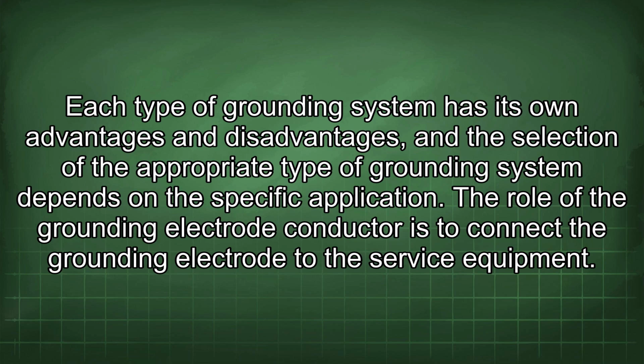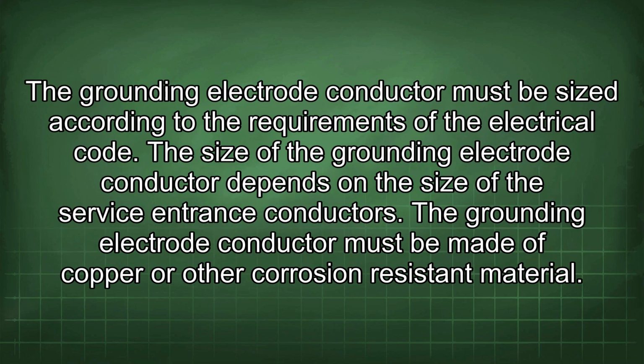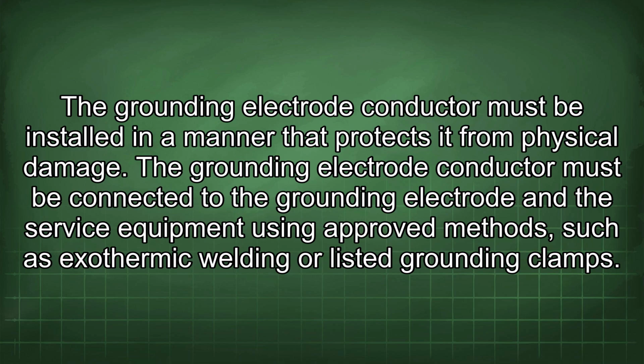The role of the grounding electrode conductor is to connect the grounding electrode to the service equipment. The grounding electrode conductor must be sized according to the requirements of the electrical code. The size of the grounding electrode conductor depends on the size of the service entrance conductors. The grounding electrode conductor must be made of copper or other corrosion-resistant material. The grounding electrode conductor must be installed in a manner that protects it from physical damage. The grounding electrode conductor must be connected to the grounding electrode and the service equipment using approved methods, such as exothermic welding or listed grounding clamps.